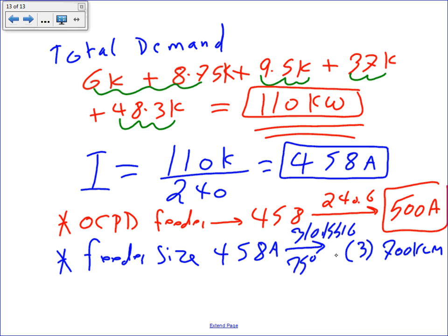So I'm taking full neutral. Here's the first size. Let's do the engineering way. So engineers size based on what? The overcurrent device. So what do you get? Chris, would there be a difference? 900. 900? Wow. That's a difference. So that would give 75, under the 75 degree column. That will give me 900. That's not much. Okay. Yeah, default is copper. So see the difference, Zach? The code allows you to go as low as 700 on this panel, or as high as sizing based on the overcurrent device.